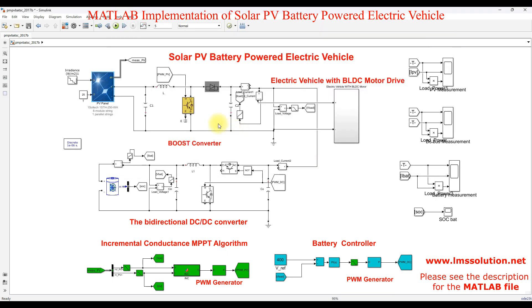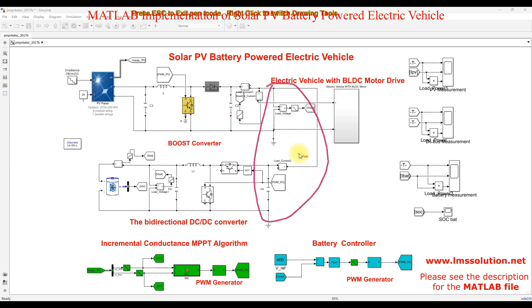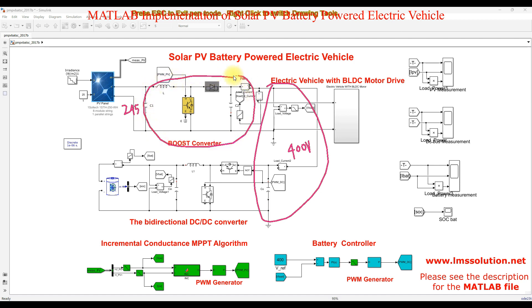The PV array will be connected to the common DC bus, where we maintain the voltage at around 400 volts. The PV array outputs around 245 volts, so we use a boost converter here to step up the voltage to 400 V. This boost converter is controlled by means of an MPPT algorithm.